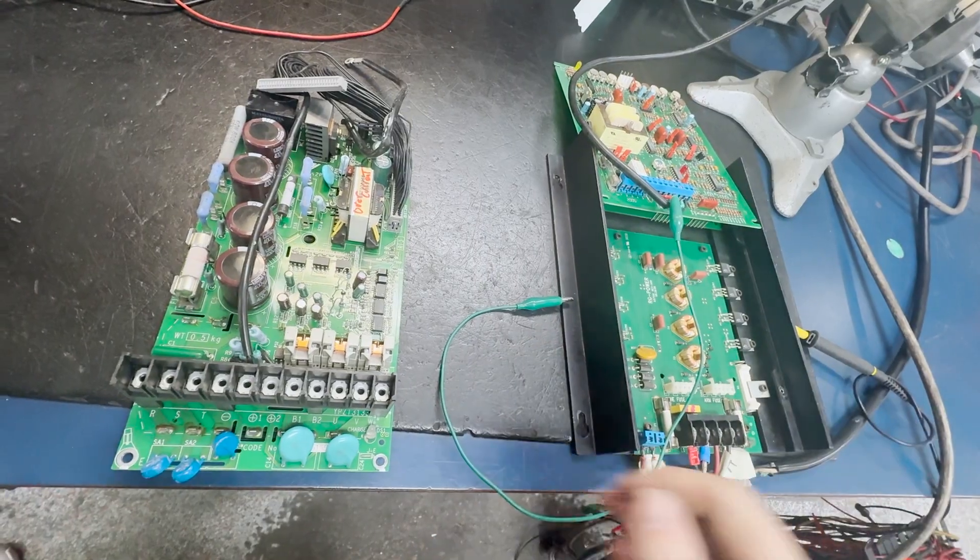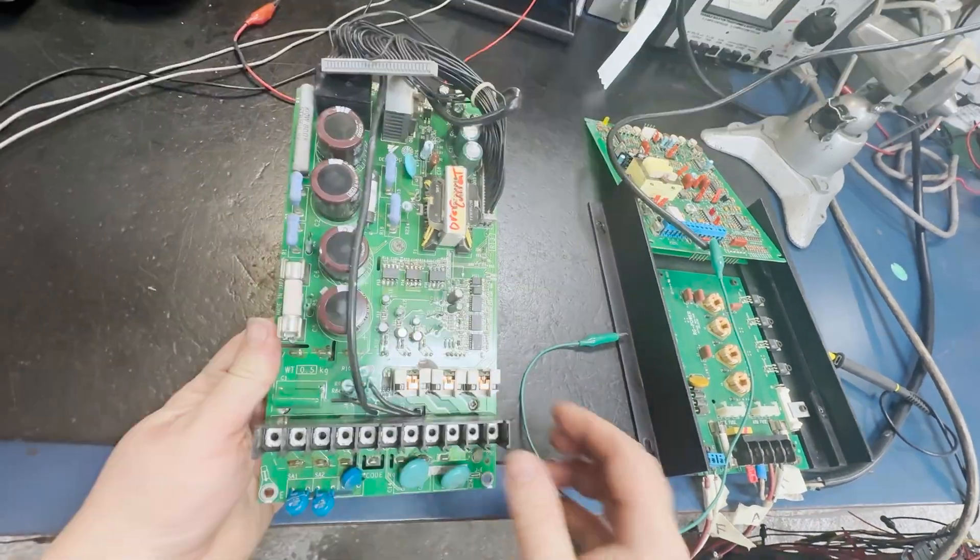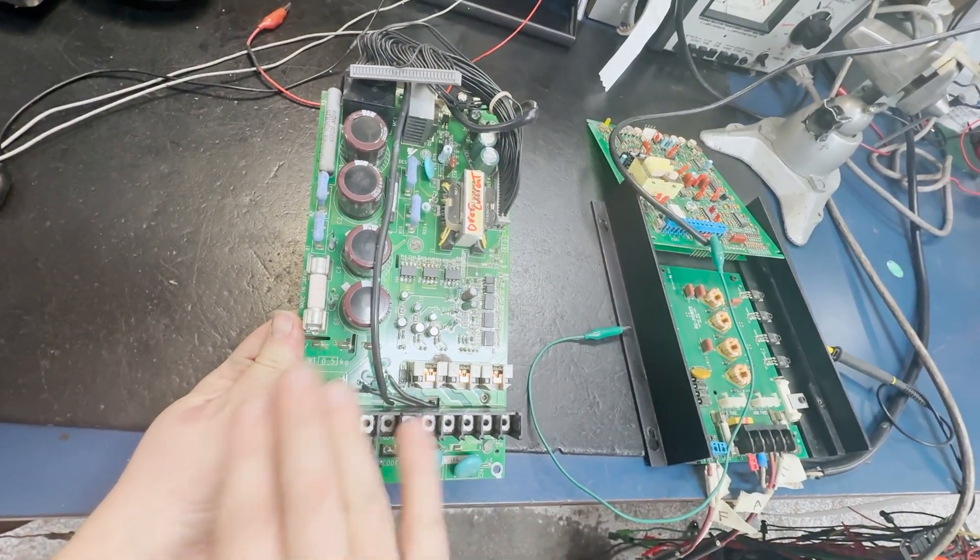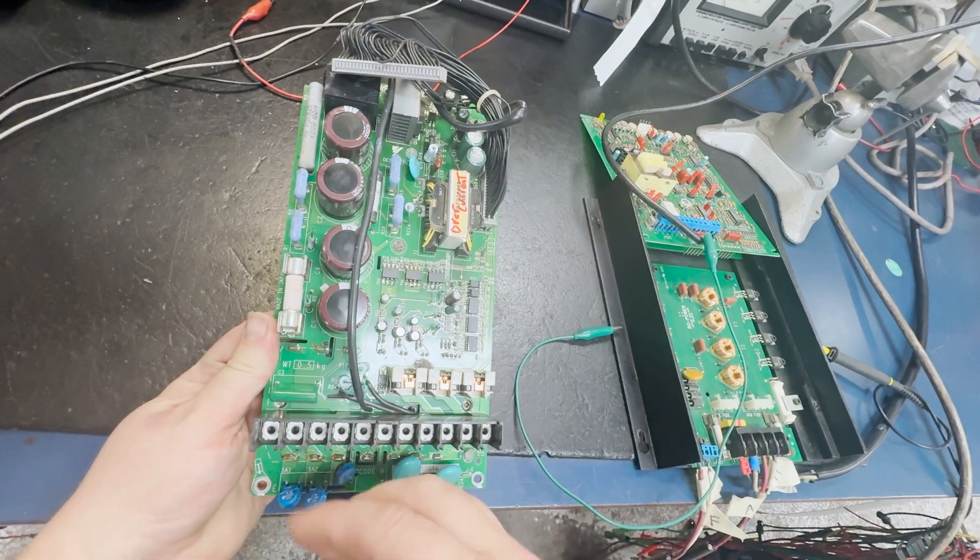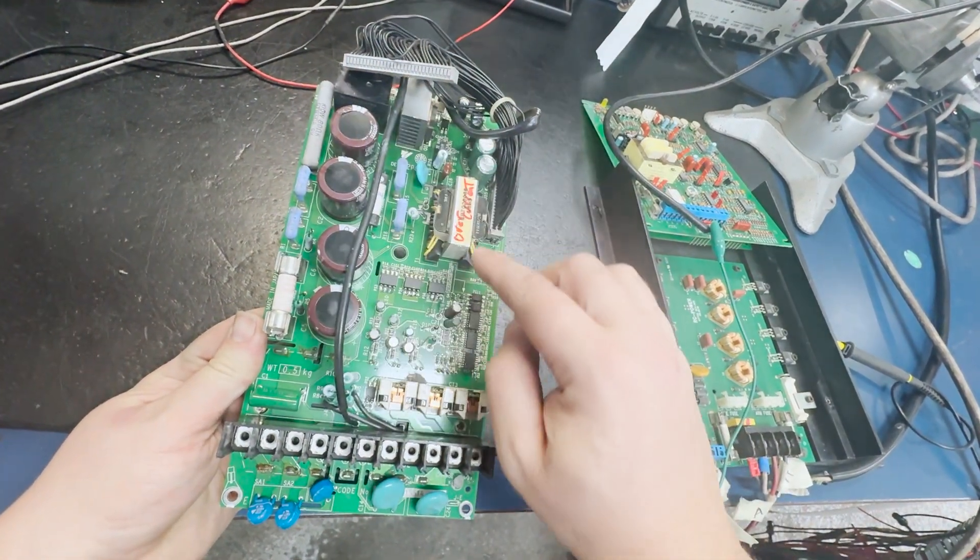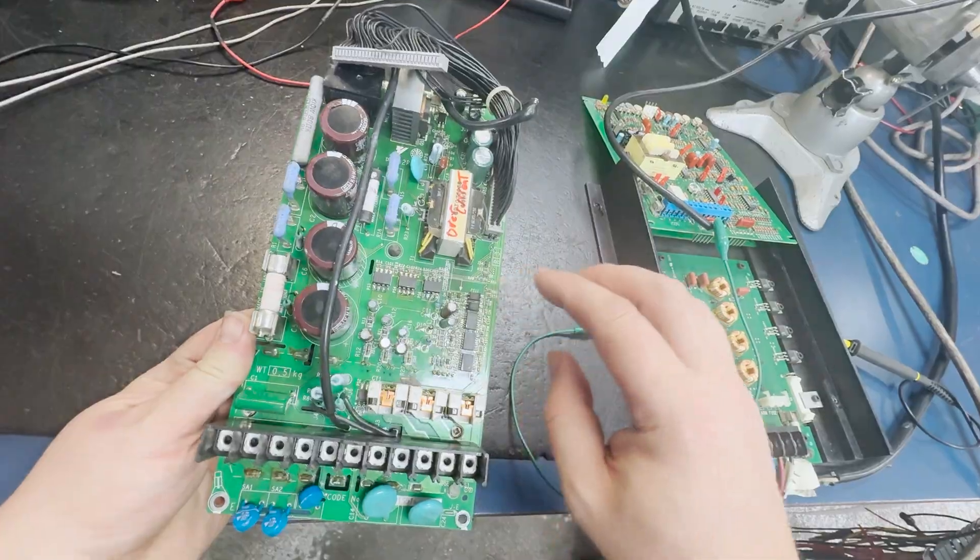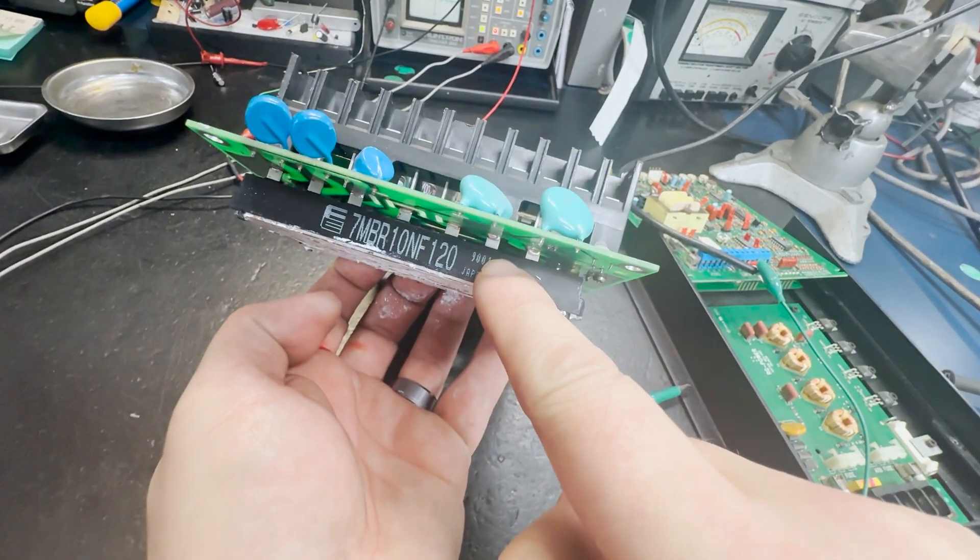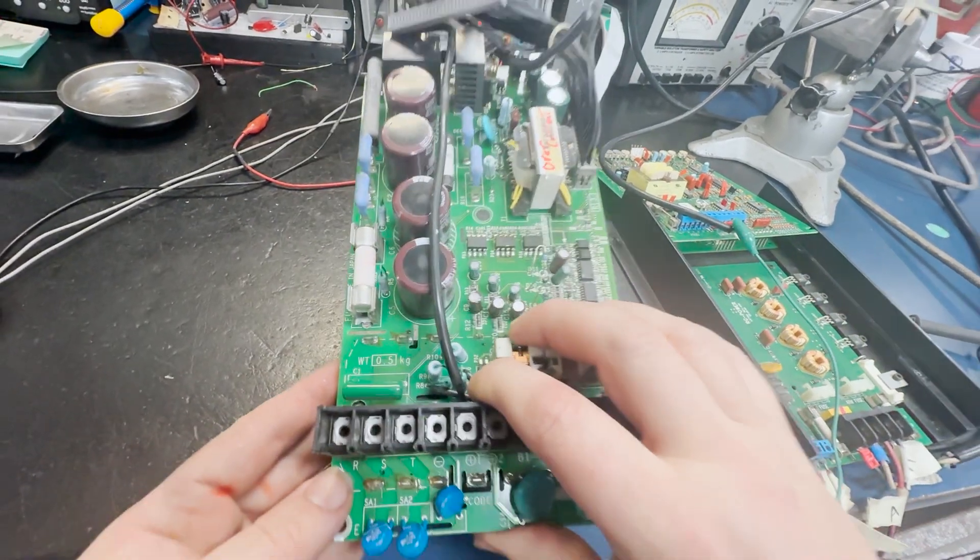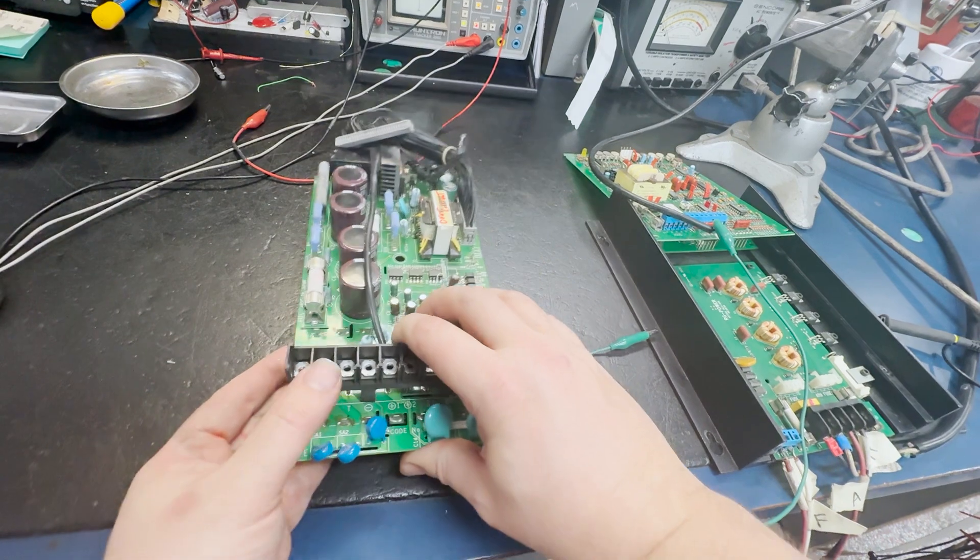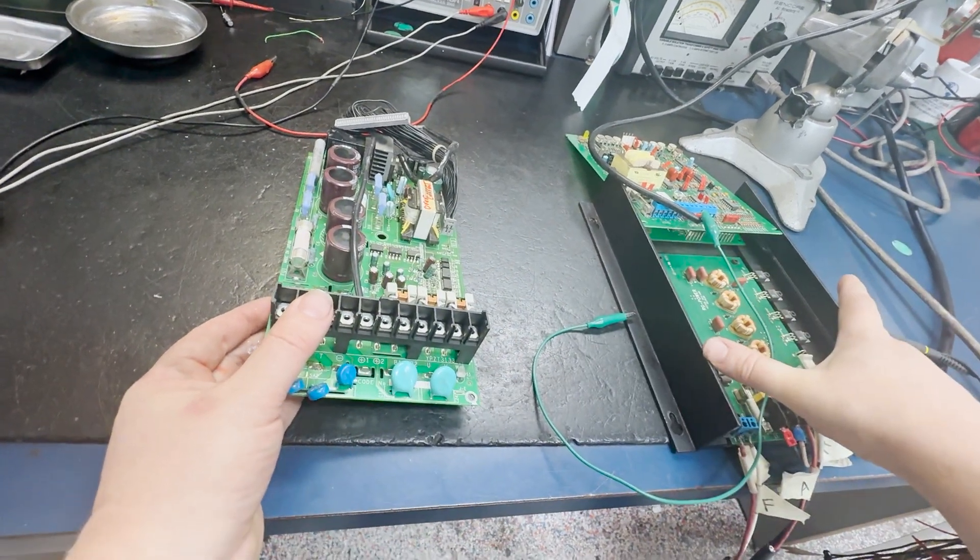Here we have a power board to an AC drive. An AC drive works by taking an AC voltage into the input, rectifying it, putting it on a DC bus, and then inverting it using gate circuitry and an IGBT, insulated gate bipolar transistor for the output. An AC drive is far different from a DC drive in this respect.